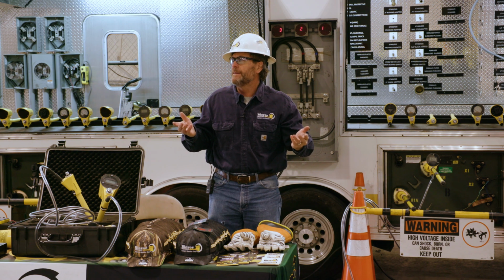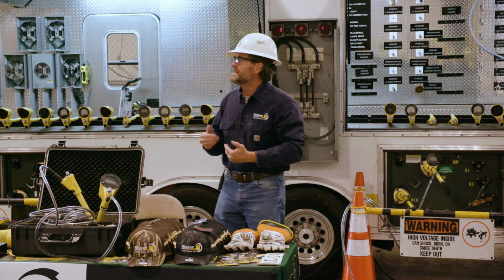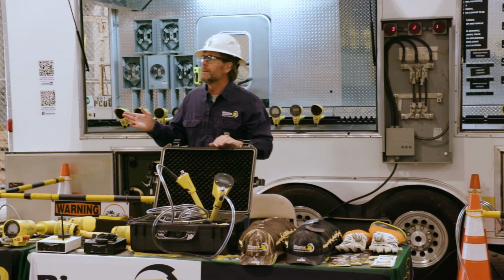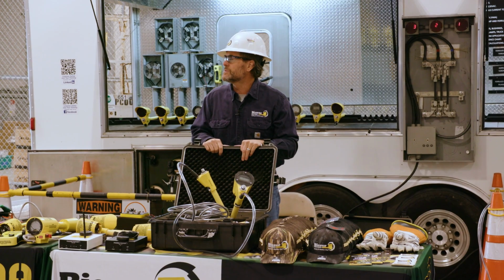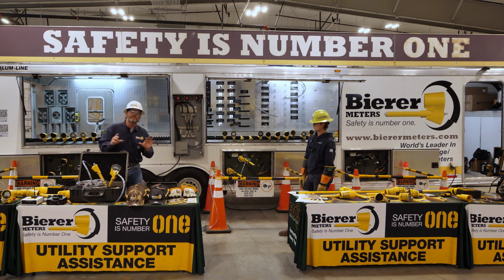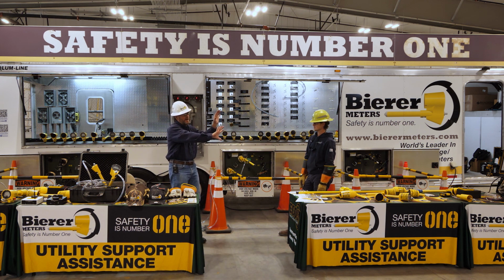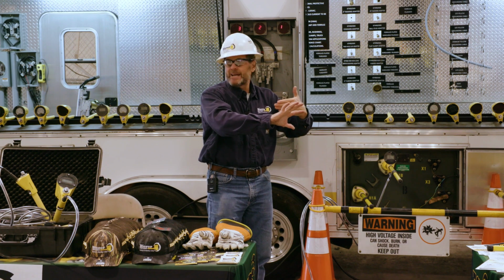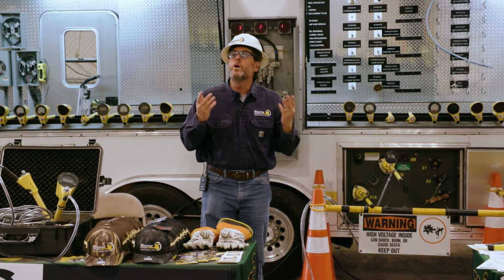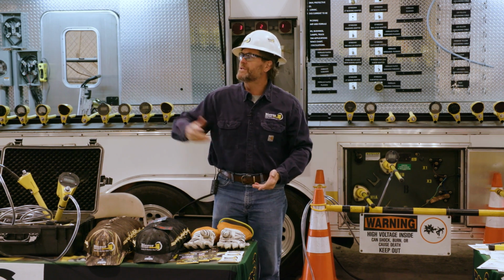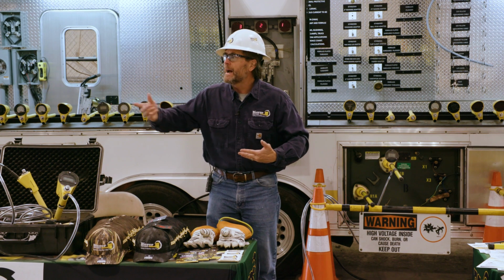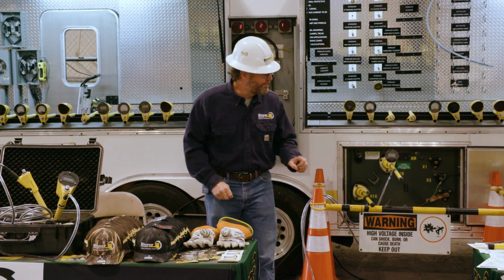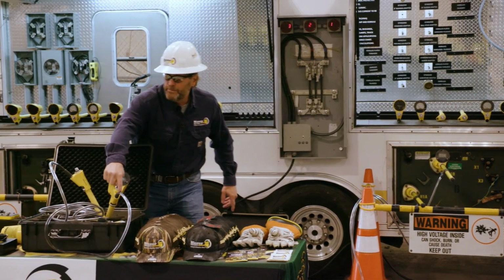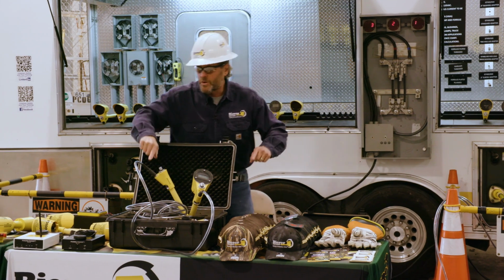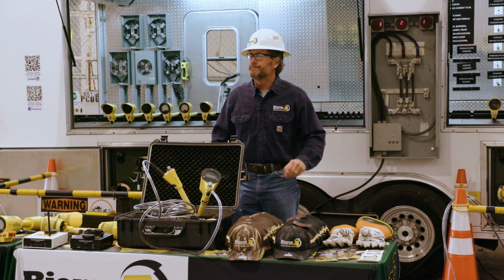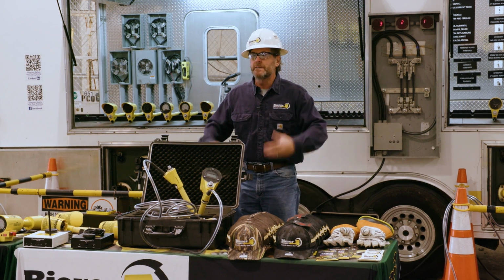They had an arc flash, right? And that's what happened. They called the shop and said, hey, your tool's no good, we need to get a replacement — maybe we need to start using somebody else's tools. So they showed us the photo, and sure enough it showed the tool making contact — the hot bus is next to the meter head, and the meter is almost against it. So no one had ever trained them on how their tools function. They didn't know. So they had an arc flash, and the guys, thank goodness, when it happened, it blew up at the meter probe, that interconnect cable. The meter probe blew up, it blew up at the secondary probe, and the cord in between was all burnt in pieces and charbroiled — just disintegrated into black ugliness, okay?